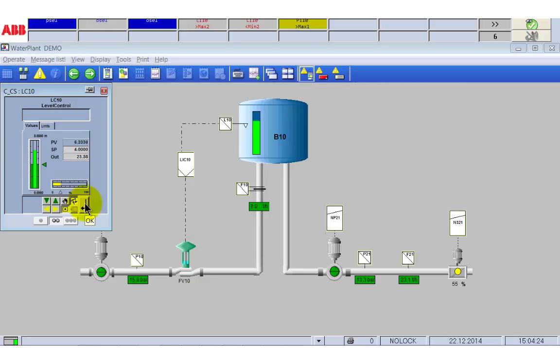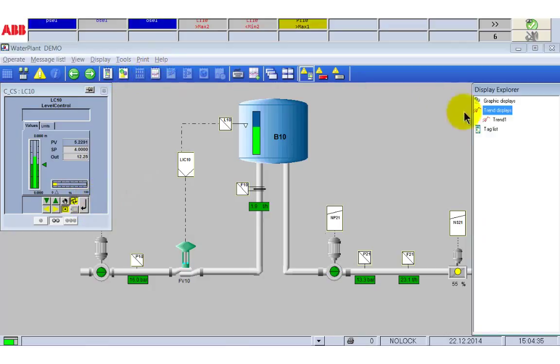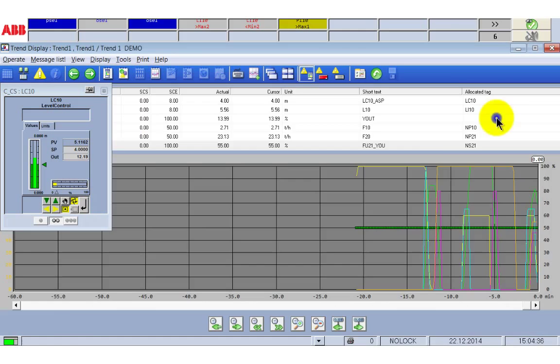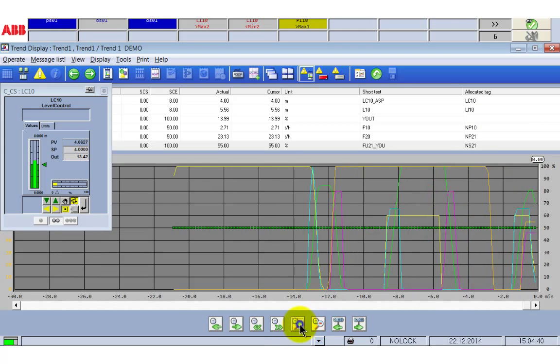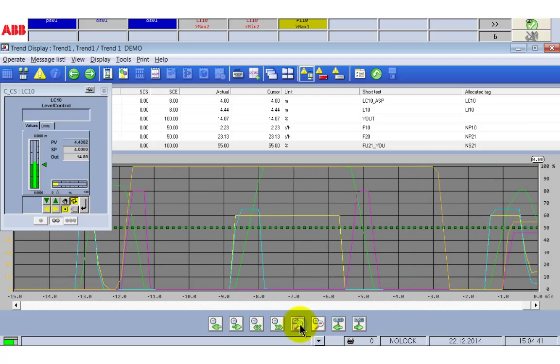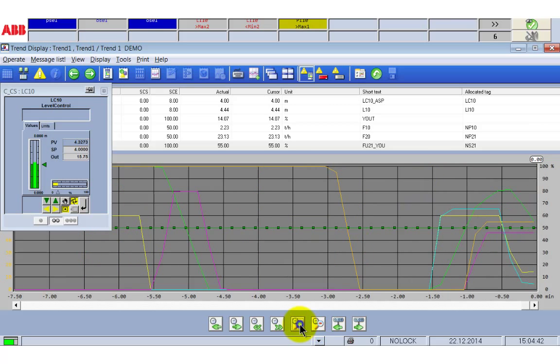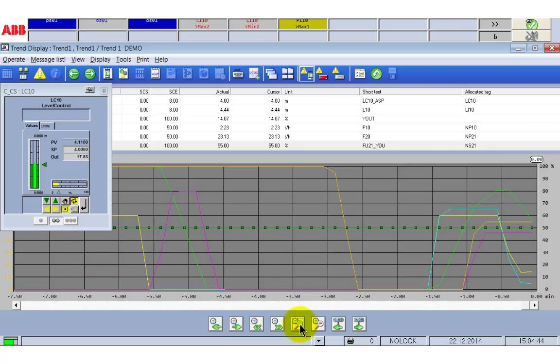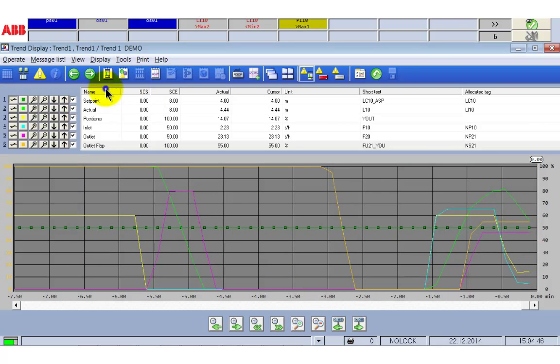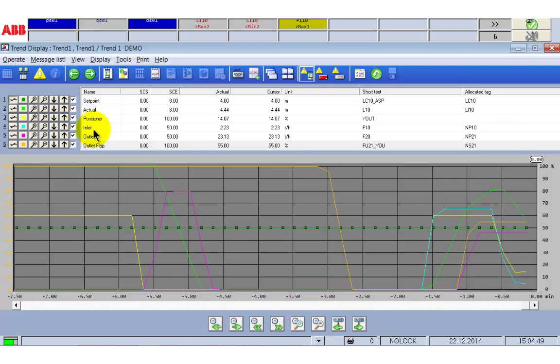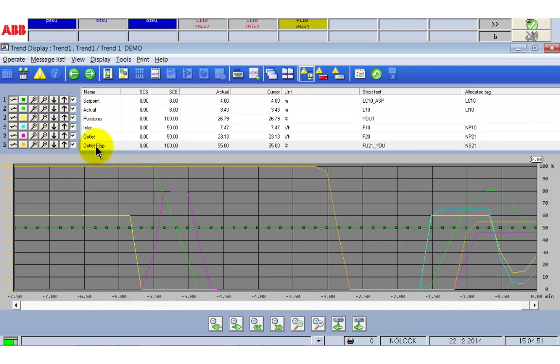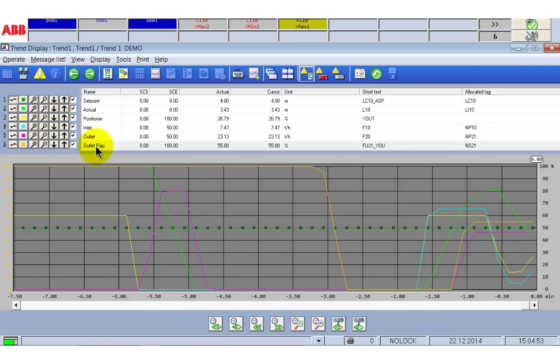You see the values here in the plant display but even better in the trend display. To see this open the quick selection window and click trend 2. To get a better overview of this trend adjust the scaling of the time axis. The trend display shows the set point of the tank level, the actual level, the positioner value, the inlet flow, the outlet flow and the position of the outlet flap.